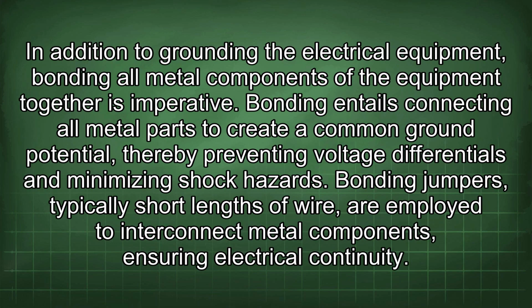In addition to grounding the electrical equipment, bonding all metal components of the equipment together is imperative. Bonding entails connecting all metal parts to create a common ground potential, thereby preventing voltage differentials and minimizing shock hazards. Bonding jumpers, typically short lengths of wire, are employed to interconnect metal components, ensuring electrical continuity.